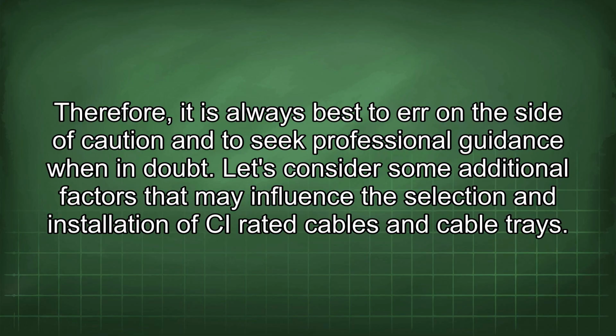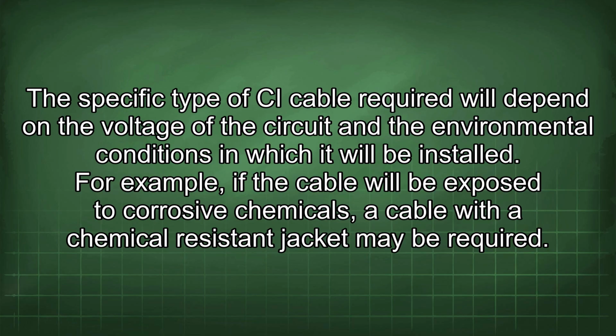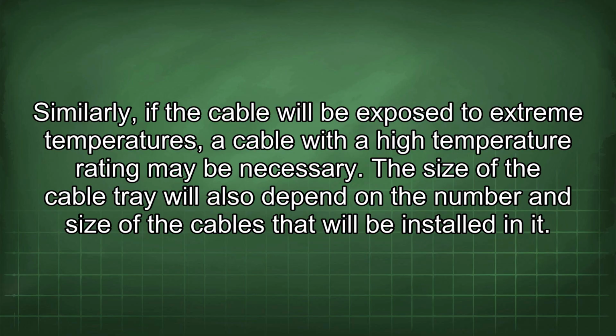Let's consider some additional factors that may influence the selection and installation of CI-rated cables and cable trays. The specific type of CI cable required will depend on the voltage of the circuit and the environmental conditions in which it will be installed. For example, if the cable will be exposed to corrosive chemicals, a cable with a chemical-resistant jacket may be required. Similarly, if the cable will be exposed to extreme temperatures, a cable with a high temperature rating may be necessary.